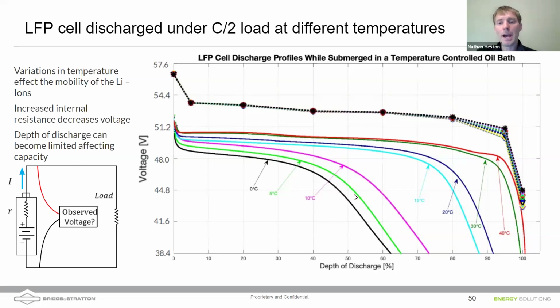That energy is still there in the battery. The charges are still on that anode side ready to go to the cathode side, but I'd have to heat it up in order to get to acceptable voltages. You can see that if I had a battery at 0 degrees Celsius and I was discharging it quickly, I'd hit my 48-volt low battery cutout when the battery is still at a 75% state of charge or a 25% state of discharge. So keep that in mind. If you store your batteries in cold environments, you're going to have less usable energy in them at fast discharge rates. If you discharge slowly, it shouldn't cause as much of a problem.